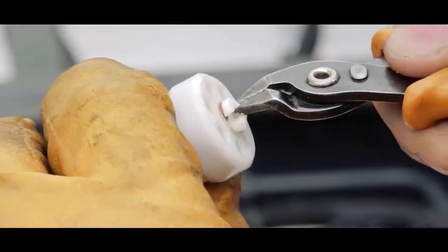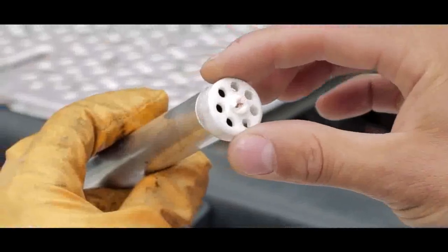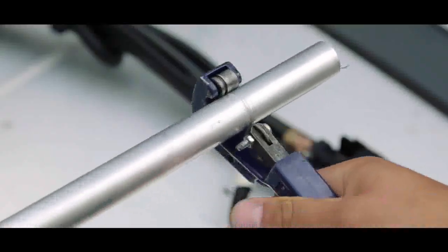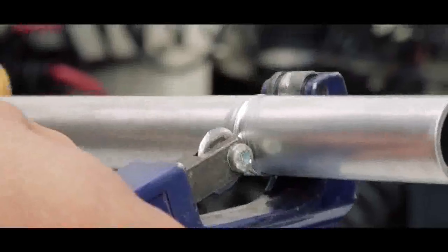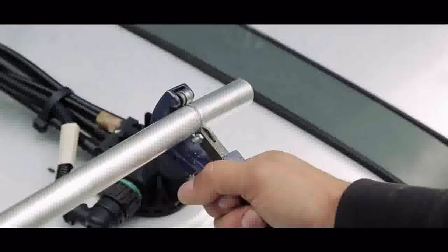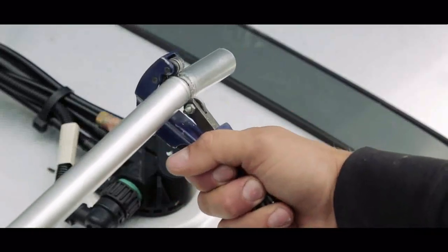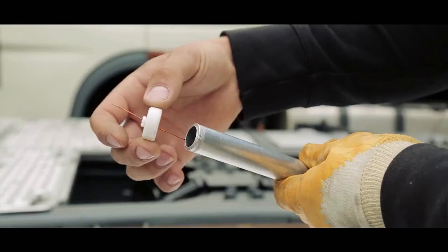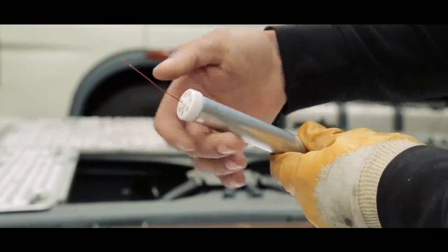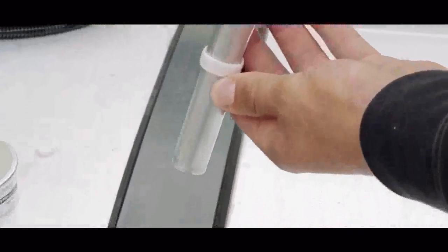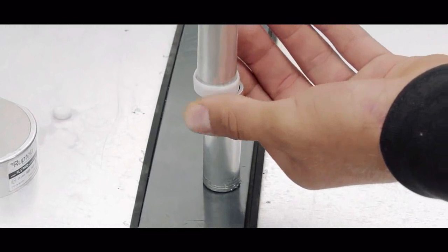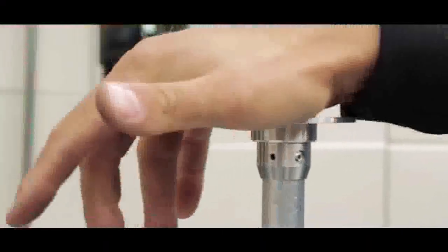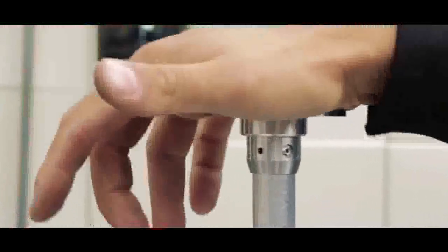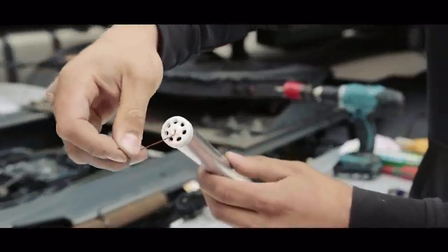Wind the wire of the bottom white cap and take the cap off. Cut the probe at the marked place with a special tube cutter. It is very important not to damage the wire that is inside the probe. When the unnecessary part of the probe is gone, put the wire through the white cap. When it is done, the cap must be pressed hard to consolidate completely. To do that, it is best to use the leftover part of the probe so that the wire won't be damaged. Tighten the wire and wrap it like this.